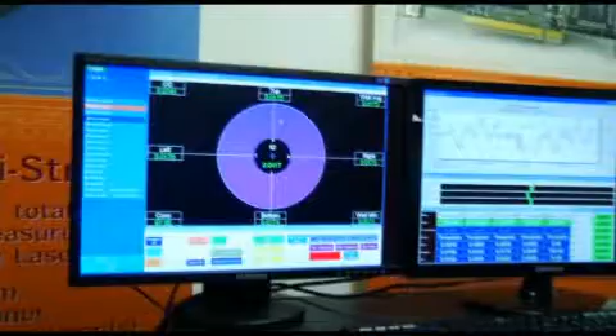So this is a model or a demo, yes, of as if you were measuring an extruded part like this, right? Correct. Okay. This would typically live right on the extruder and often be used to feedback and control the extruder, to control the wall thickness in real time. Yes, by either changing the puller or changing the airflow.